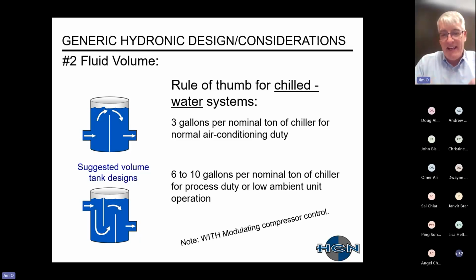What they recommend is you add a volume tank or maybe oversize some piping to add volume to your chiller. Just want to point out that for your volume tank, you want to add baffles inside so that the water actually does mix and doesn't travel from the inlet to the outlet. And then once again, a rule of thumb is that if your cooling system is for what I'll call normal HVAC or air conditioning duty, you want to have about 3 gallons per ton. But if you have a chilled water system that you're using for process or for low ambient, you want to increase that to 6 to 10 gallons per ton.